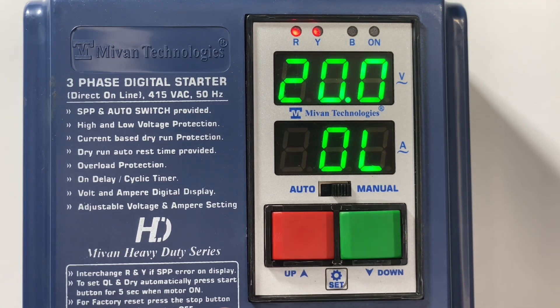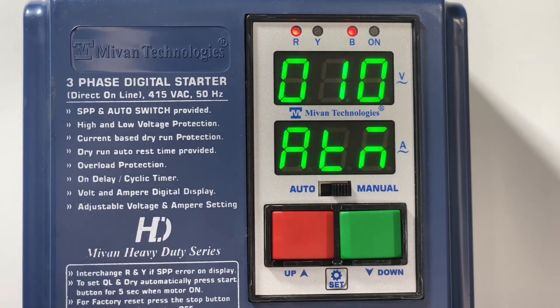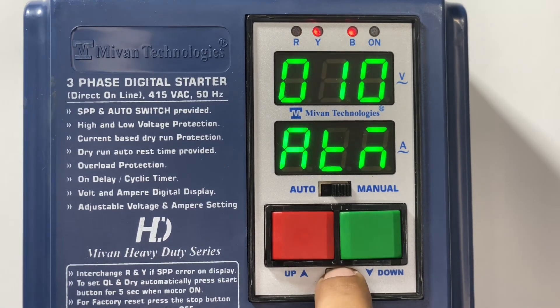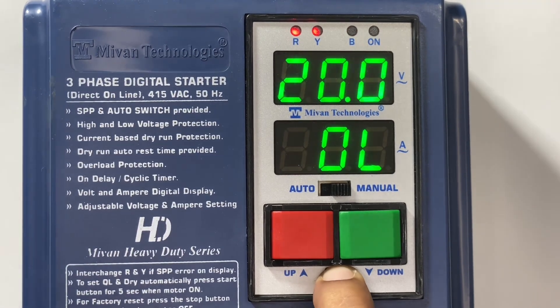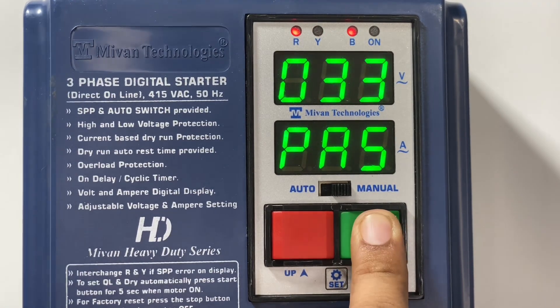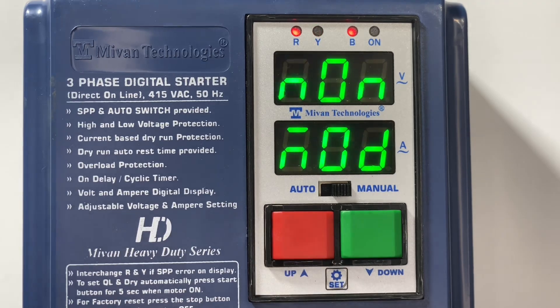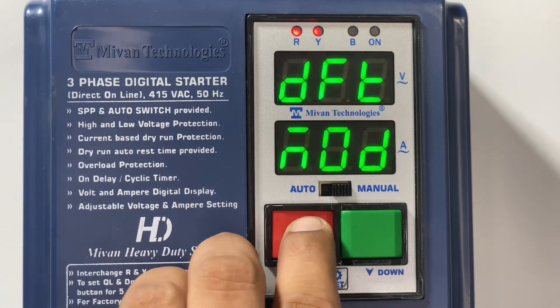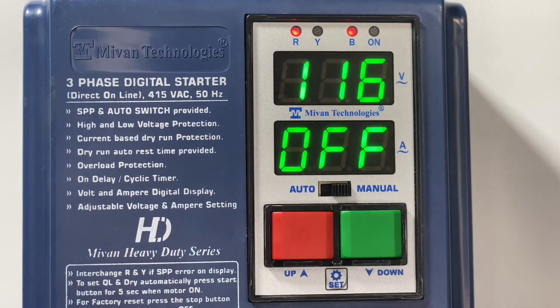Press the set button in the main menu — you can see the overload option. Press the set button again and you can find the auto timer option, also known as the auto switch on delay timer. To enable the cyclic timer, press and hold the set button for 5 seconds and enter the password: 33. Press the set button, press it again, press it once more and you can find the mode option. In this mode option, select cycle mode to enable the cyclic timer. Press the set button to come back to the main menu.